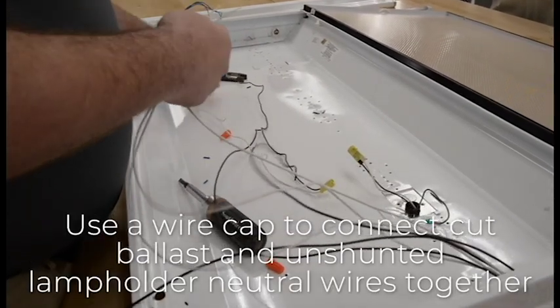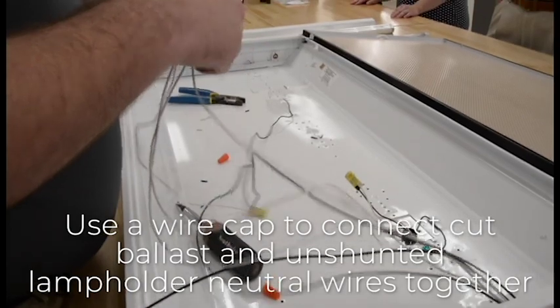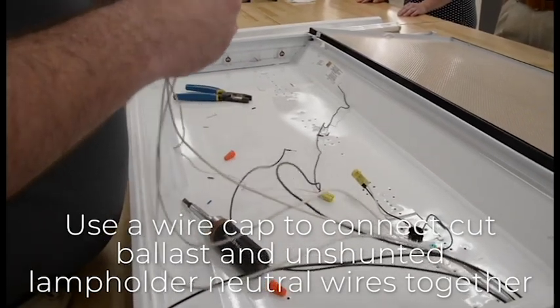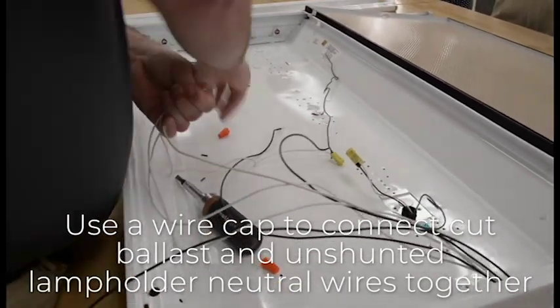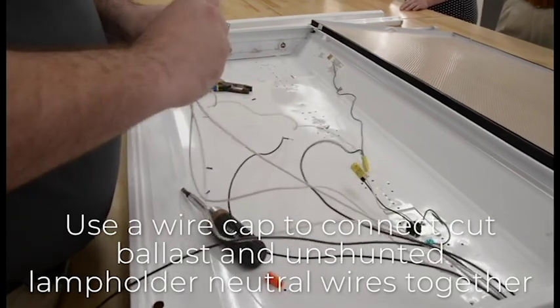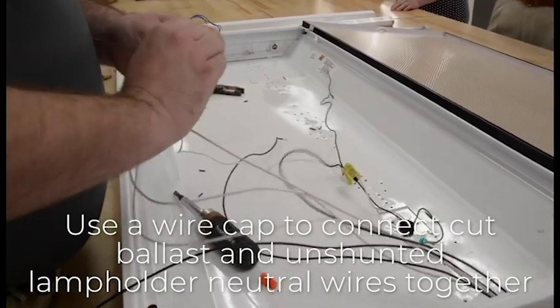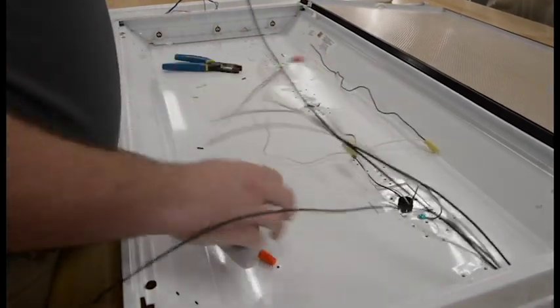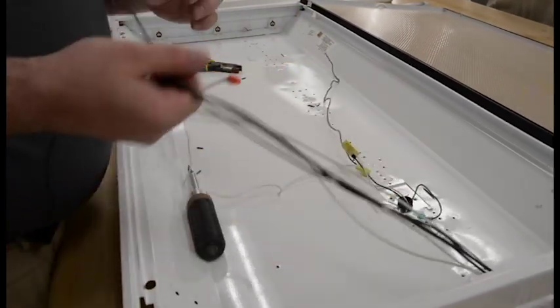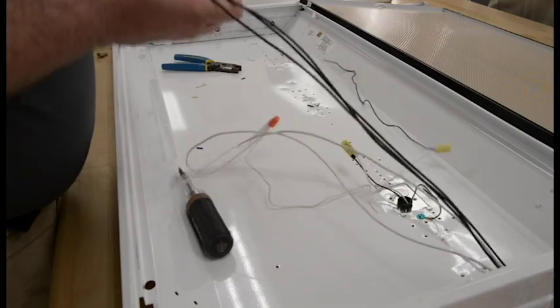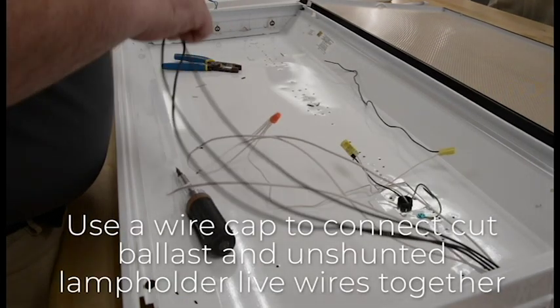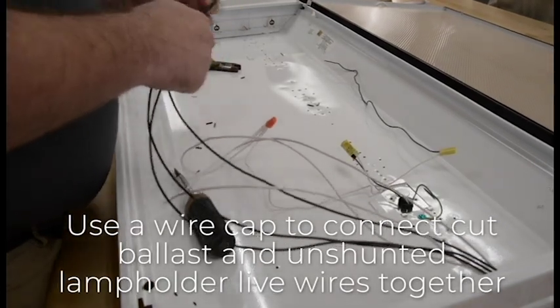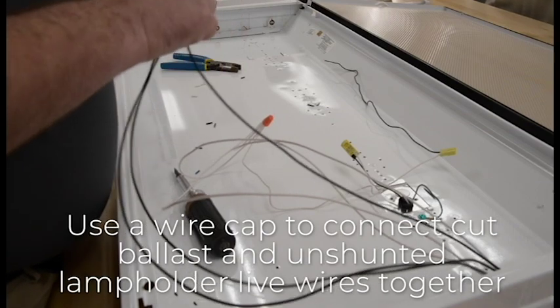On the unshunted lamp holder, connect the neutral wires with the fixture's neutral wires that we previously cut from the ballast using a wire cap. Also connect the live ballast wires to the unshunted lamp holders' live wires using a wire cap.